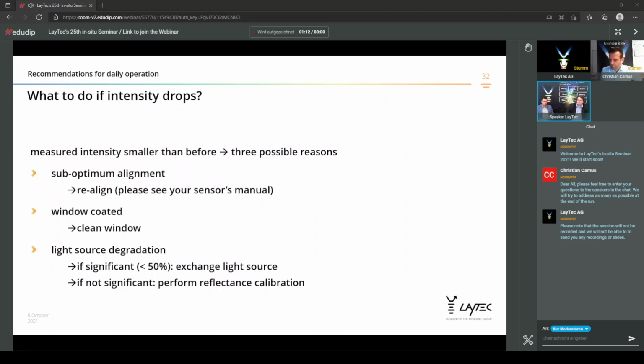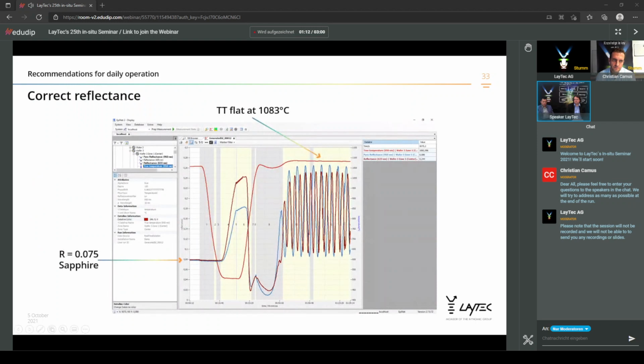As long as the light source degradation is not so significant, it's a slight decrease, this is normal lifetime, so over time the intensity will decrease. You need to perform the reflectance calibration. This will compensate this effect. So, what does correct reflectance calibration mean? In that case, we show it for the sapphire wafer. On the substrate, we expect a reflectance of 7.5%.